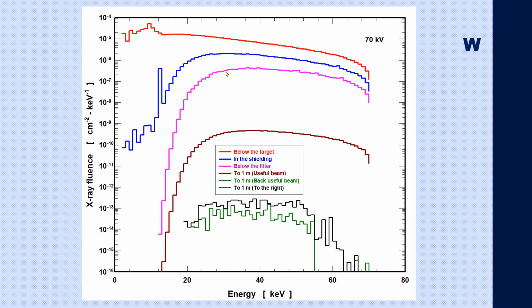And when we pass through the filter, the filter eliminates all these low energy photons, and these are the photons in the detector that is allocated just below the filter. And the spectrum that reaches 1 meter has this shape, and you can notice that the amount of photons at 1 meter is reduced by several orders of magnitude, approximately 1, 2, 3, 4, 5 orders of magnitude. And these two spectra represent those spectra of X-rays that leak out from the shielding of the X-ray tube. The black one is the detector that is allocated to the right. The green one is the spectrum that is allocated in the rear part of the X-ray tube.